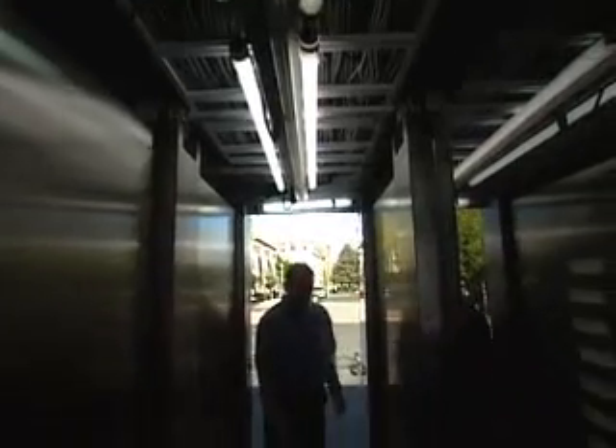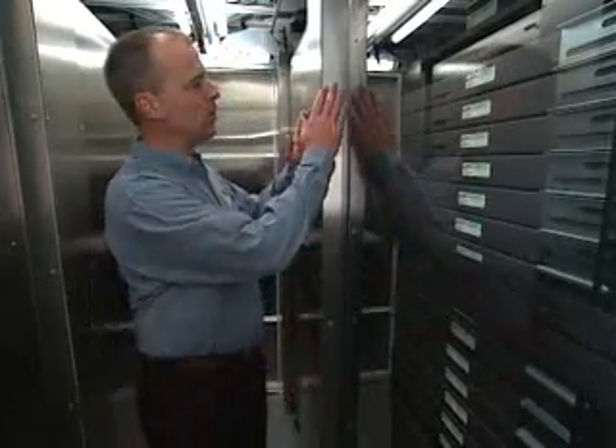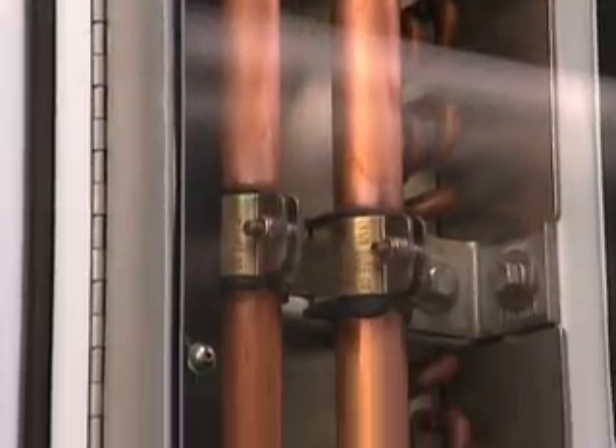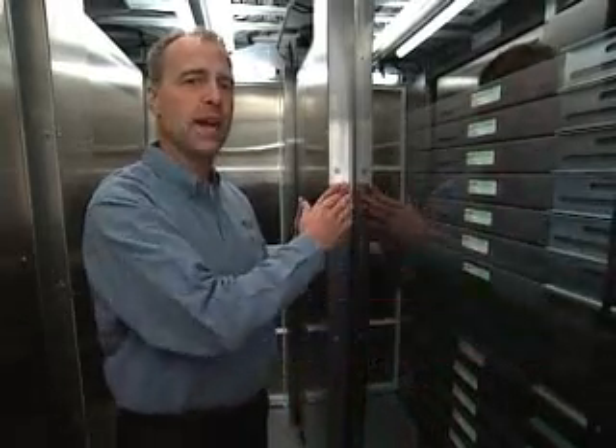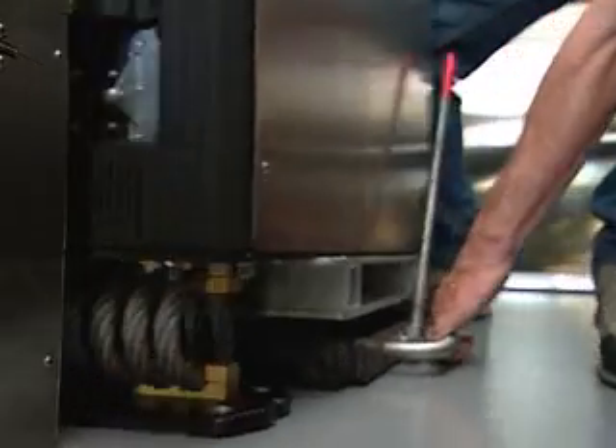Let's go inside and take a look at the racks in more detail. It's a little noisy in here — that's just because of the wind blowing in order to cool the servers. We've got cooling for 200 kilowatts worth of servers, and all that's going through chillers that sit in between each rack. This is a standard 19-inch rack that holds 42 rack units worth of servers. It's mounted sideways so that we can blow air through it from front to back and then immediately through a chiller before it goes to the next rack. These racks pull out into the aisle, and you can service them from both the front and the back.